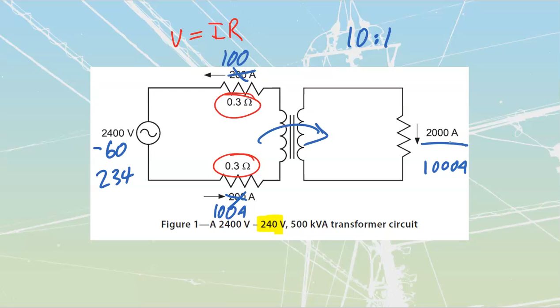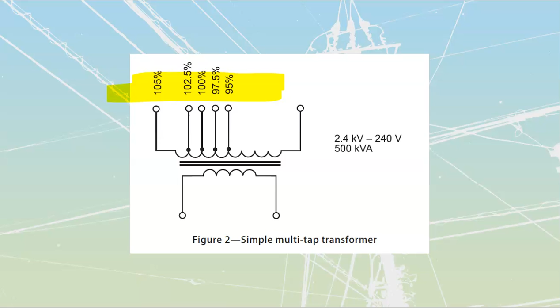What we will have on those type of transformers is percent taps. And the lovely thing about percent taps is simply that they tell us what my incoming voltage is going to be, based upon the amount of line drop. So what we do when we are monitoring these is, let's say that I've got a customer that's getting a low voltage out over here on this side, and he's got those two lines that are being fed in. I'll let you draw them in here with just proper lines a second. So that's the incoming lines.